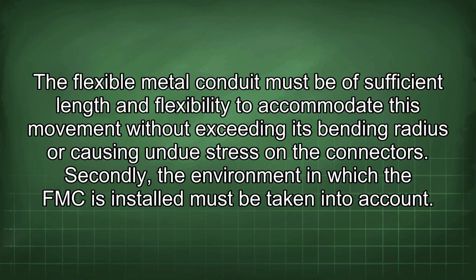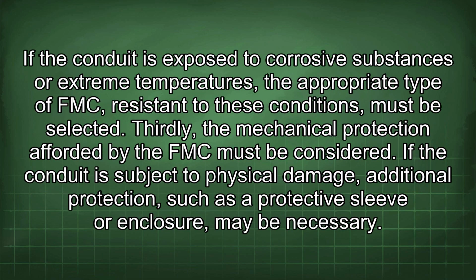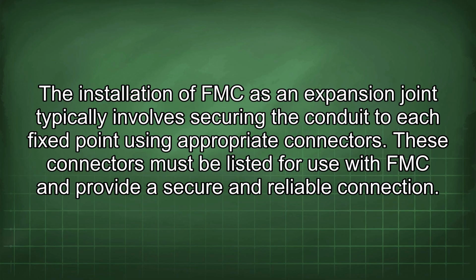Secondly, the environment in which the FMC is installed must be taken into account. If the conduit is exposed to corrosive substances or extreme temperatures, the appropriate type of FMC resistant to these conditions must be selected. Thirdly, the mechanical protection afforded by the FMC must be considered. If the conduit is subject to physical damage, additional protection, such as a protective sleeve or enclosure, may be necessary. The installation of FMC as an expansion joint typically involves securing the conduit to each fixed point using appropriate connectors. These connectors must be listed for use with FMC and provide a secure and reliable connection.